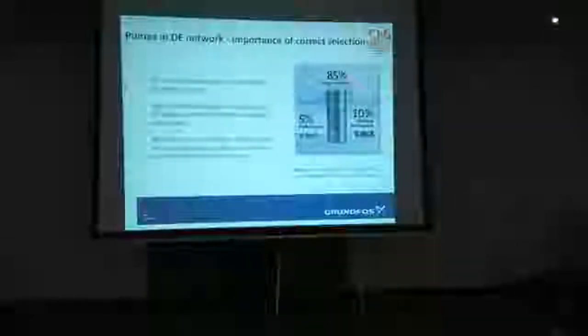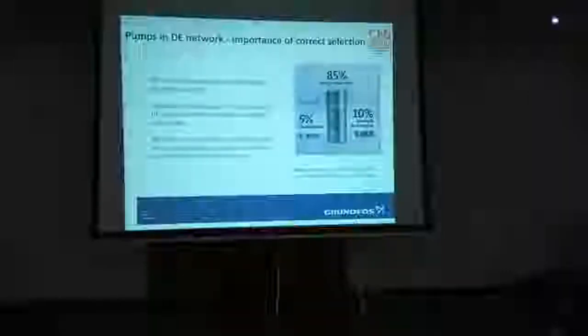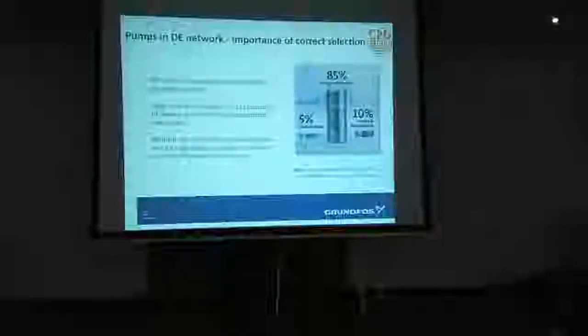That's a typical breakdown of pump life cycle costing. The installer is probably more interested in the purchase price. The ESCO, or the guy who's running the energy centre, is interested in that bit, and that bit. Not really that bit. So over 25 years, we could be looking at £1,000 to buy some of these pumps. You oversize it, get it wrong, that could be 40 or 50,000 pounds.